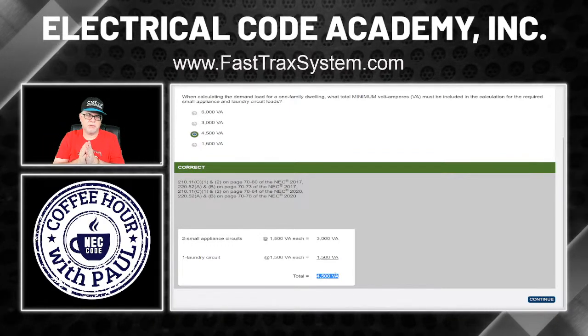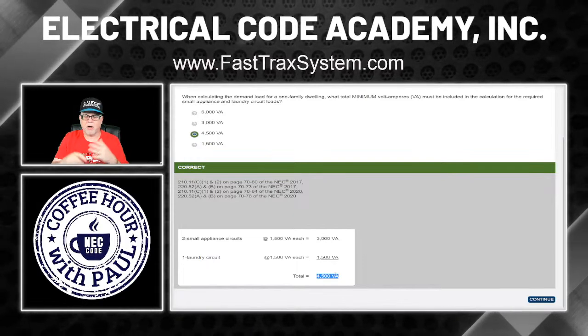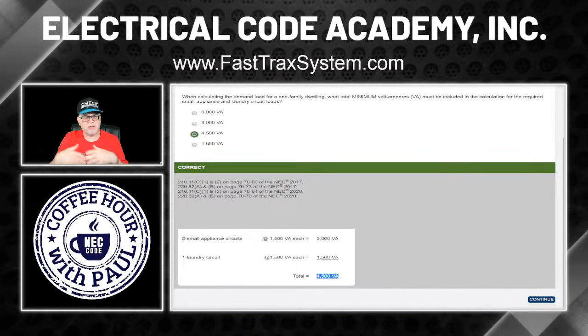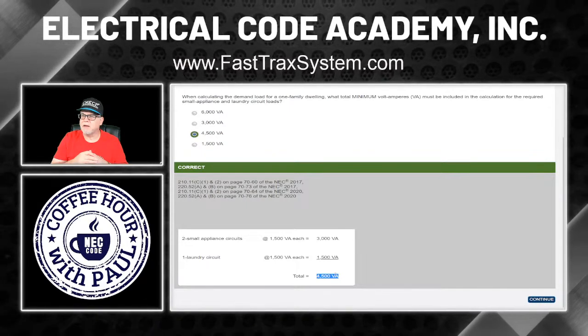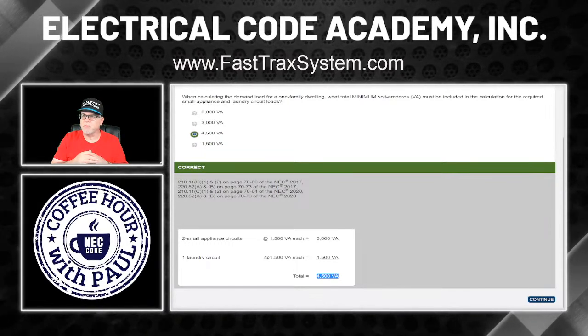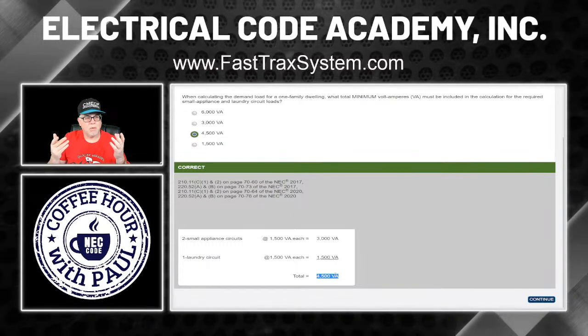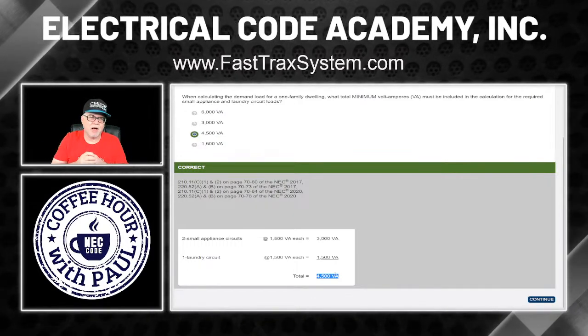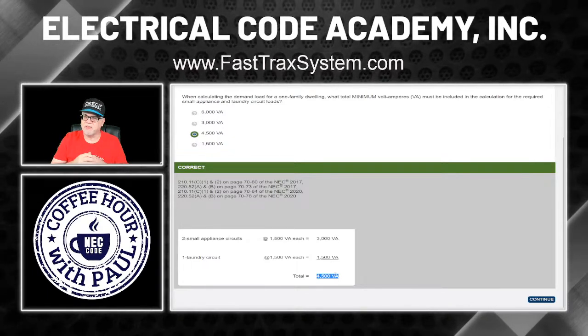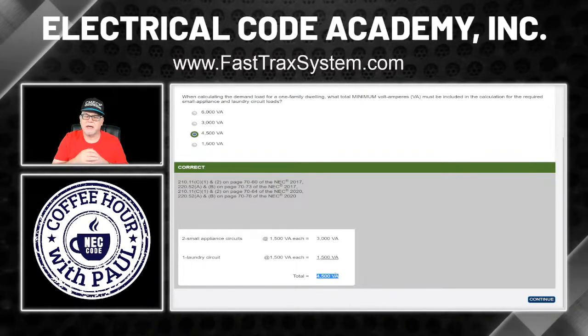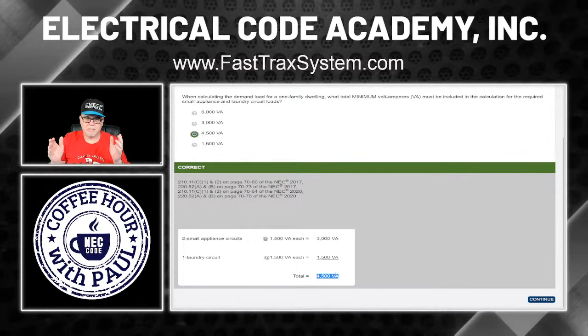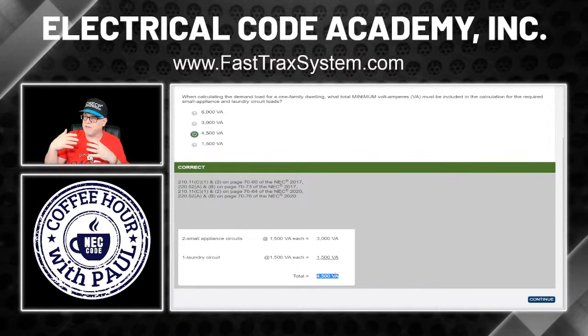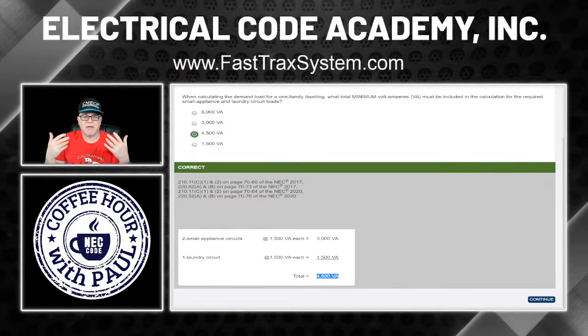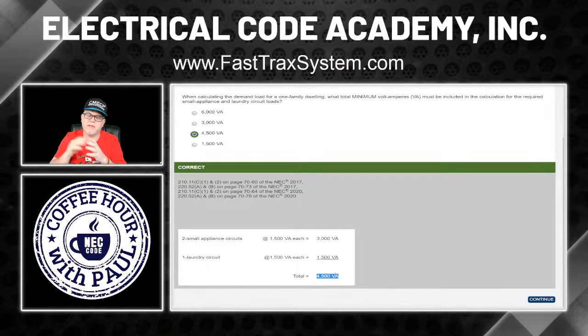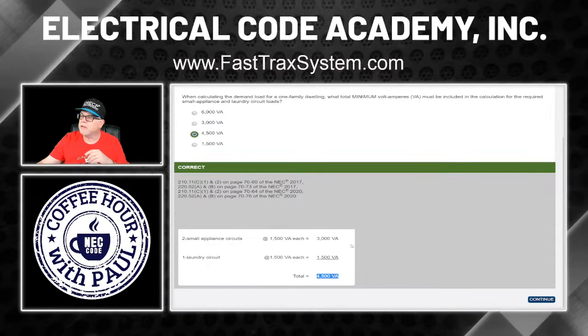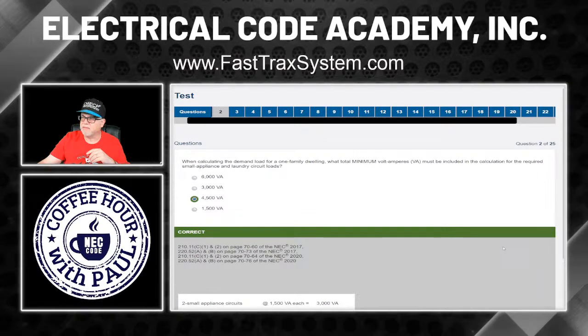All that question did, folks, was ask me, what is the demand load that I have to contribute for the small appliance and the laundry loads? Well, we don't have enough information to do anything other than pull the VA value specifically directly from the NEC, and that's it. There's nothing we can apply. We can't apply any real demands. We can't do any of that because we don't have all the variables. All we're doing is answering the question, and that's all you need to do for that. Okay, so that answer there is 4,500. Okay?